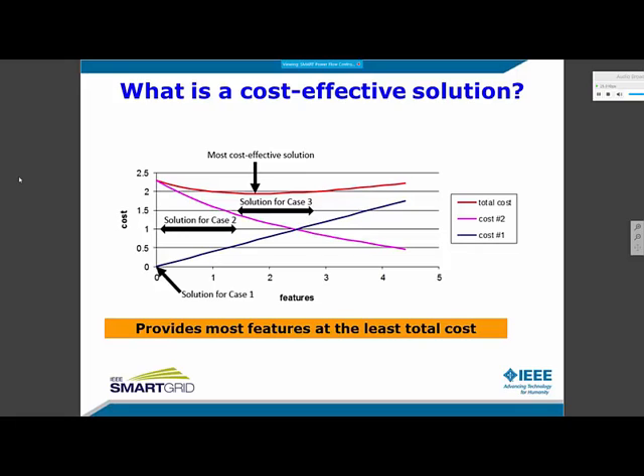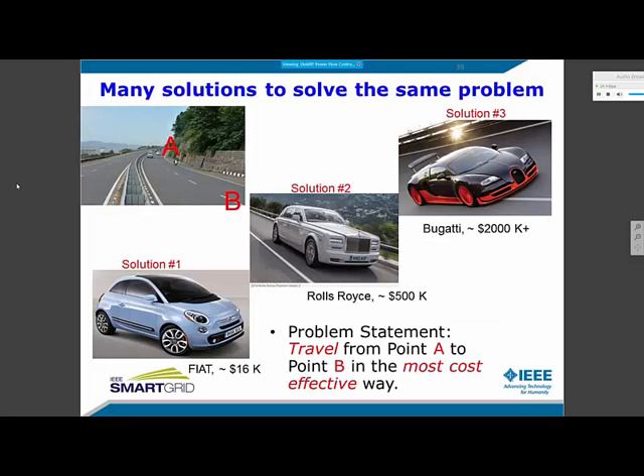That brings up a good question. What is a cost-effective solution? My answer is that a cost-effective solution provides most features at the least total cost, which consists of 2 parts. Cost number 1 is the solution cost, and cost number 2 is the other cost that includes loss, maintenance, penalty for generating flicker, etc. In case 1, if we do not do anything to reduce our flicker, the solution cost is 0, but the penalty cost is the highest. In cases 2 and 3, the solution cost gets higher as the features of the solutions increase, and cost 2 comes down because of the higher solution features. There comes a point when the total cost is the lowest, and that's when the solution is considered the most cost-effective solution.